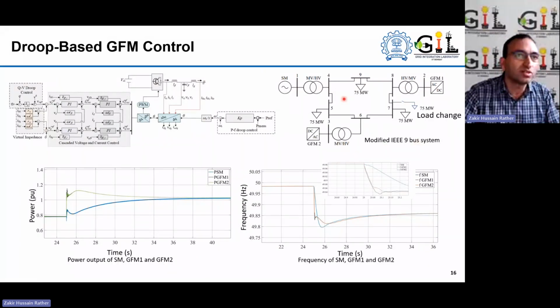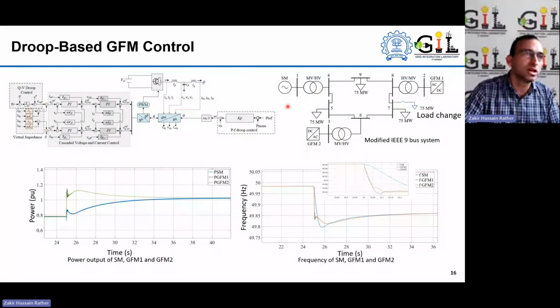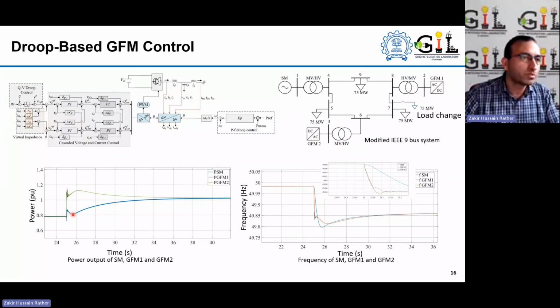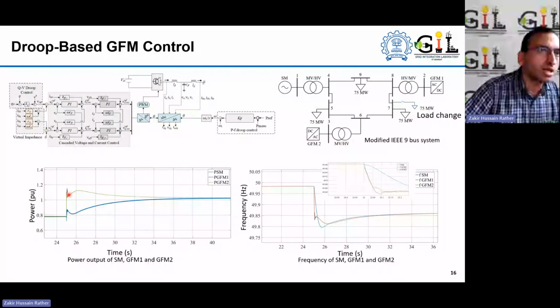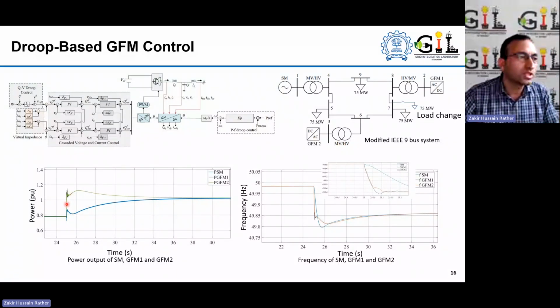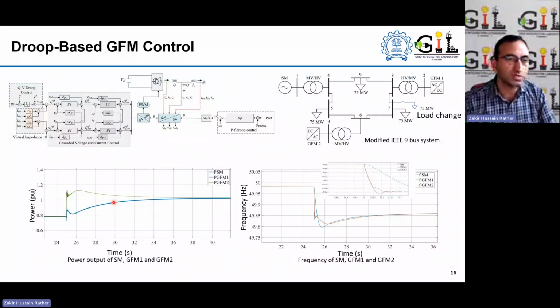We have done this kind of test to see the response of this grid forming technology. This is a small 9-bus test system, and we have a synchronous machine, grid forming inverter 1, and grid forming inverter 2. Each generator has a capacity of 100 megawatts, and then there is a load change of 75 megawatts, and you can see the response here. This is the response of the conventional generator, and this is the response of the grid forming IBR, power plants 1 and 2. So you can see it is providing a faster response, and the magnitude is also relatively better, and this is the impact on the frequency.